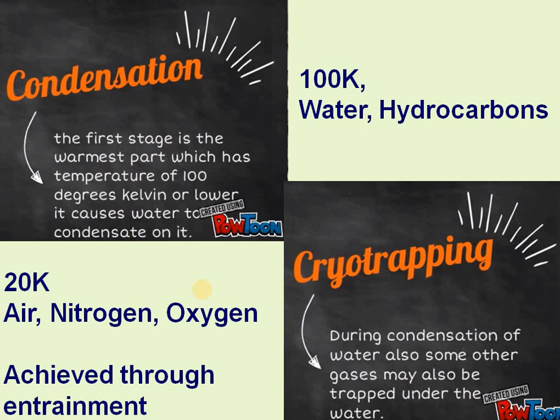These gas molecules get trapped within the water crystal because crystallization occurs at very low temperatures. Water condensed at around minus 200 degrees becomes a heavy solid in a highly crystalline state, with the ability to trap other gas molecules in its crystal lattice. So these gas molecules get embedded or trapped in the crystal lattice of water — this is what is called entrainment, a forceful dragging of gas molecules from the chamber.